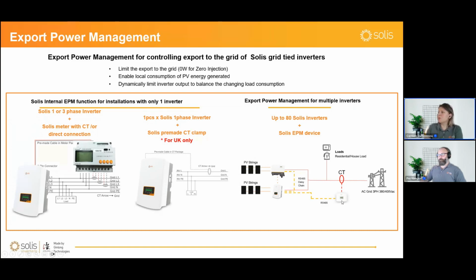This EPM will act just like a meter. It will monitor the export of energy to the grid, but at the same time it will also control all of the inverters connected to it and control their output, so that all of them react at the same time to either lower or increase their generation, just so that no excess energy goes out to the grid besides what you are allowed, what you have set up as maximum output.